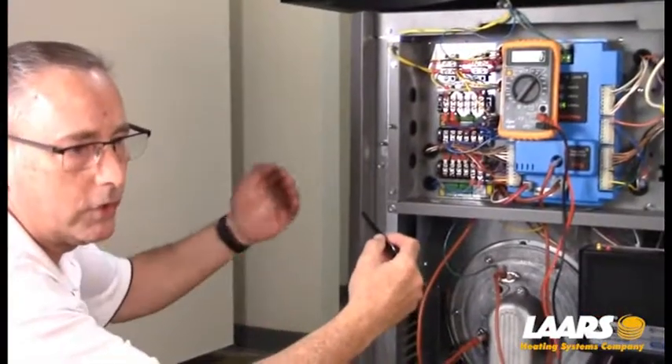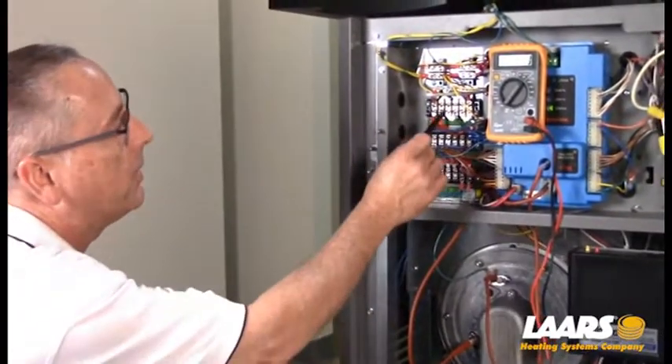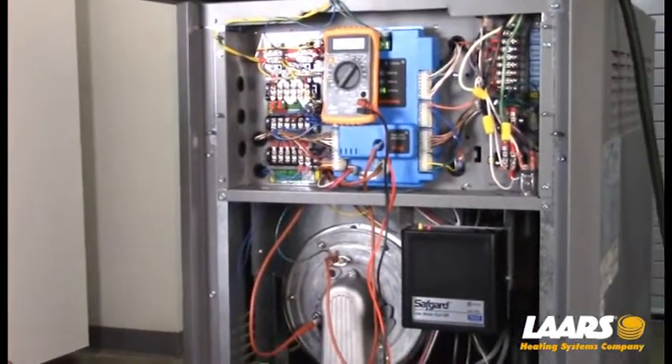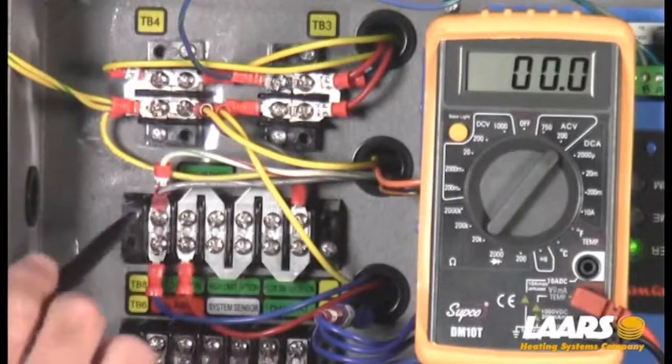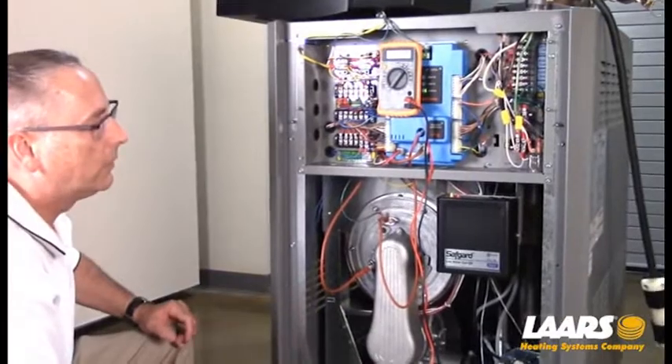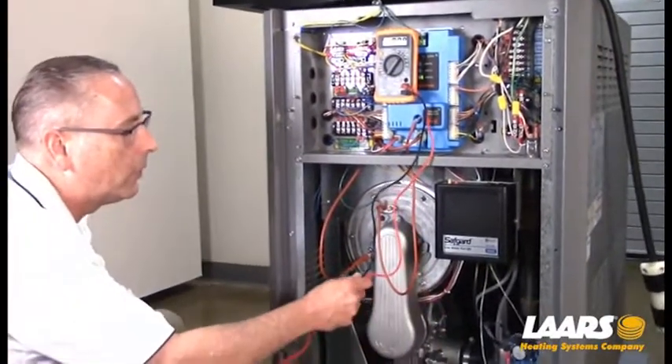Some states require additional high limits installed in the piping. In this case we have a Safgard low water cutoff which is tied in, and then the safety chain goes off to the high and low gas pressure switches, fusible links, and condensate switch.